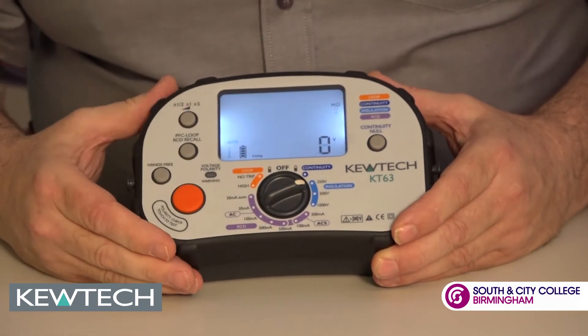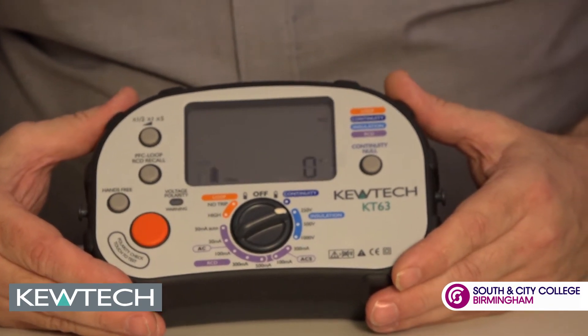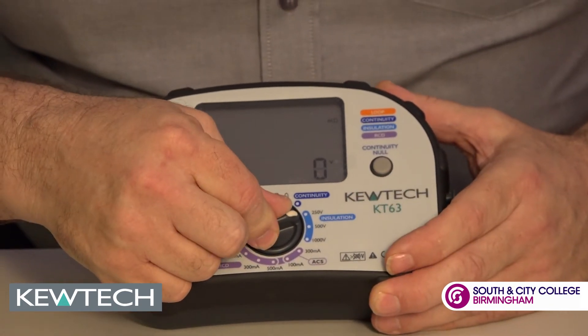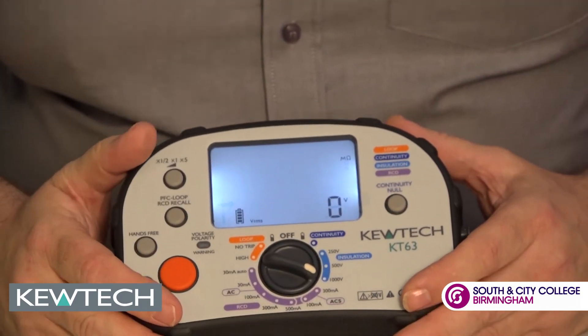Moving round, we've got insulation resistance. Again, we can use that with our PAT adapter should we want to do dead PAT testing. And all we simply do to go between the voltages — 250, 500, and 1000 — is just turn the dial. Couldn't be any easier.